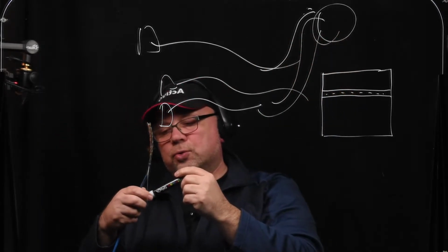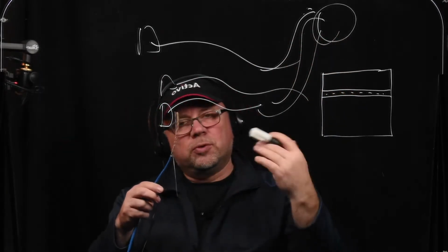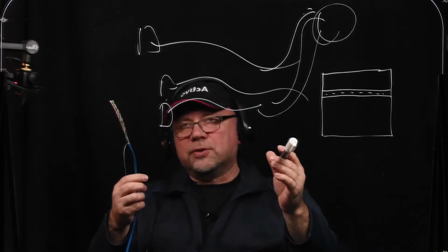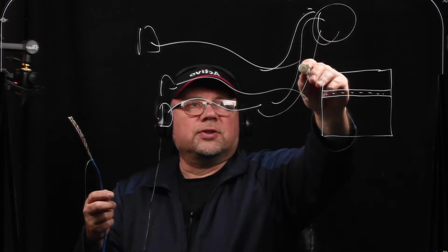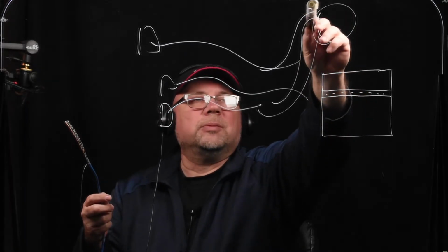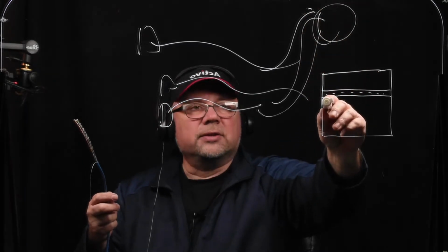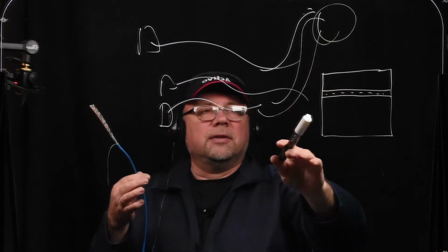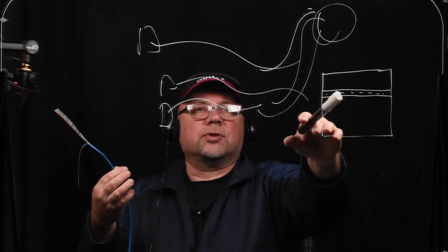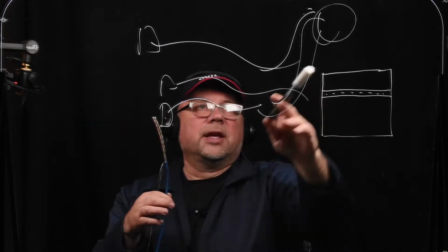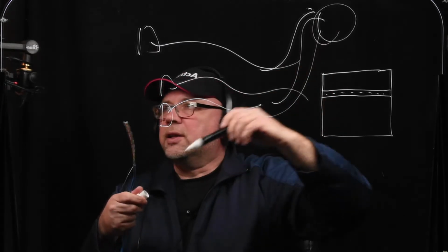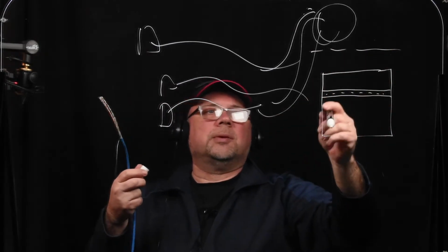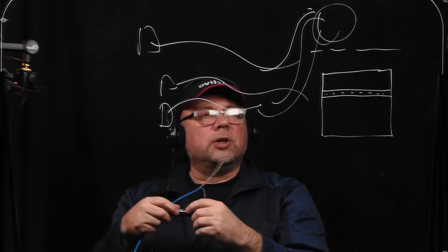Now, yes, there are different schools; some people are going to tell you to always have a service loop. Basically, what a service loop is, you just run an extra length and loop it around maybe once or twice, and then you run it right into the rack. That gives you the possibility of pulling extra slack if you need to troubleshoot, or something gets damaged, or you're running out of length. You are going to be able to grab that from that service loop, which is basically right above the ceiling here, or maybe right above the rack, equipment rack, somewhere in the communications room.